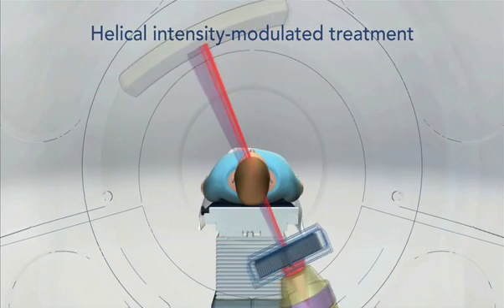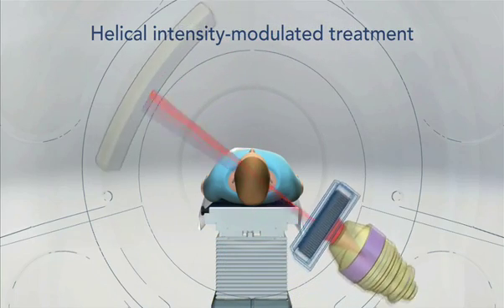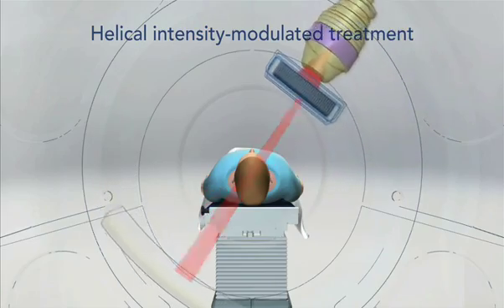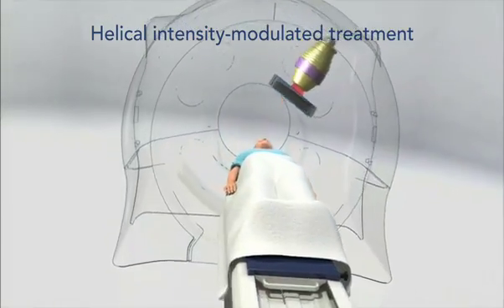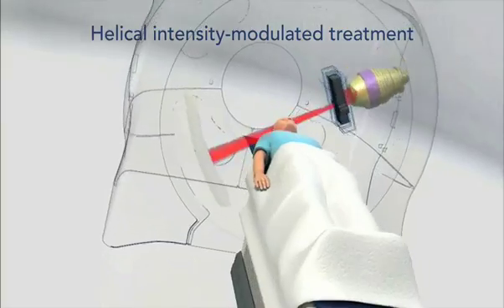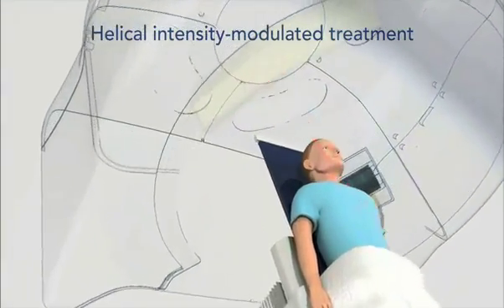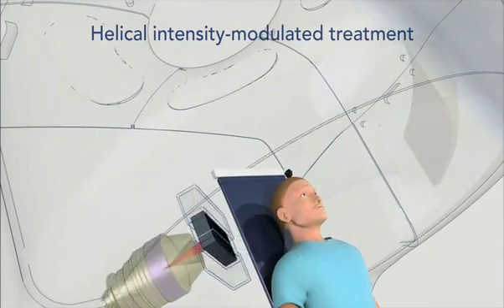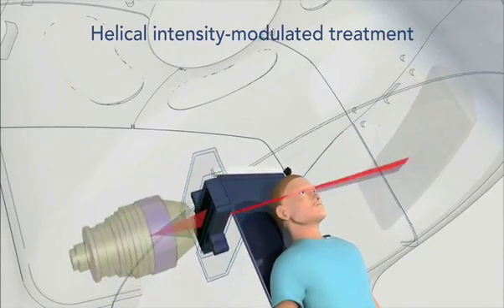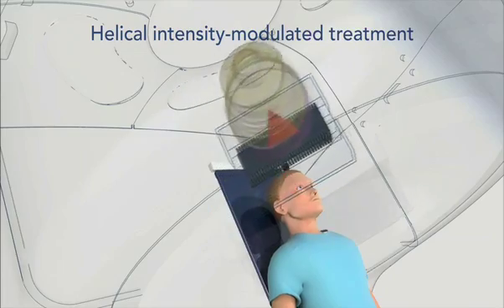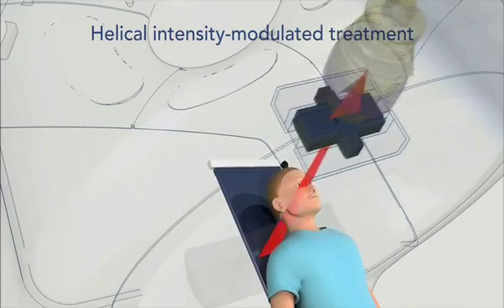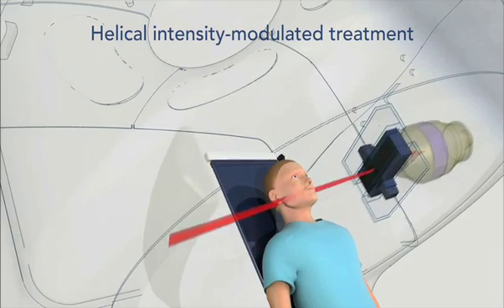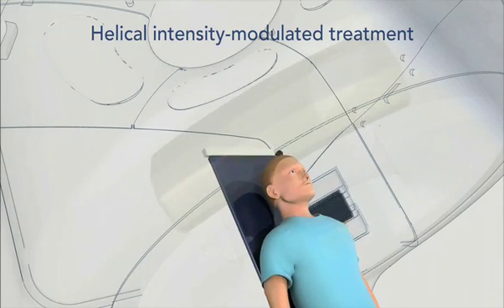The 64 leaves in our unique binary multileaf collimator create tens of thousands of optimized 6mm wide beam elements known as beamlets. This unique combination of a helically rotating beam source and beamlet-based delivery is what distinguishes TomoTherapy treatment from other forms of intensity-modulated radiotherapy.